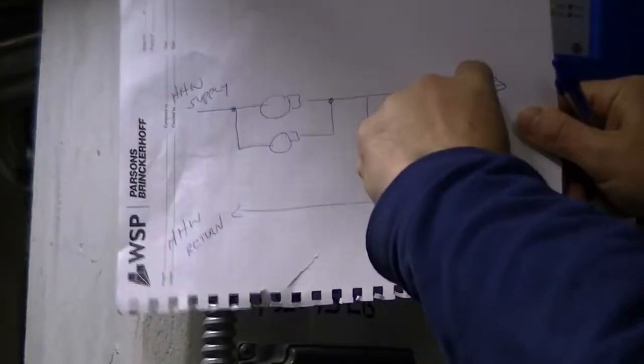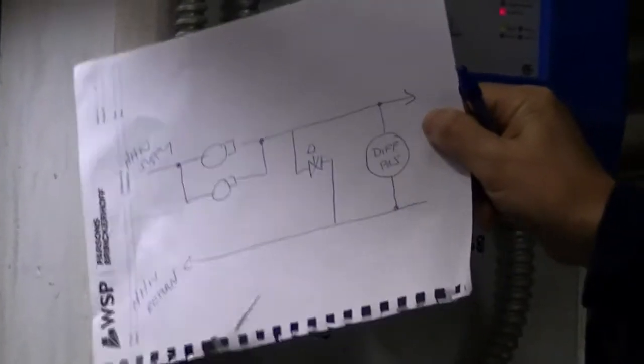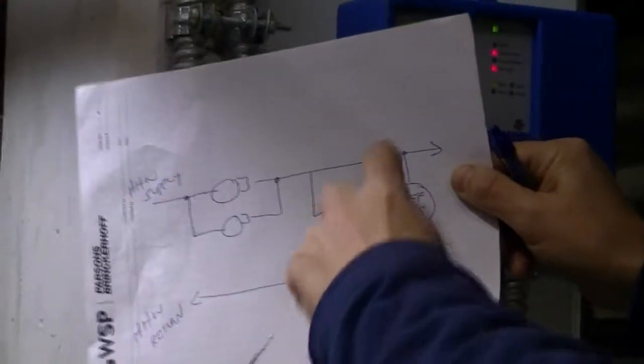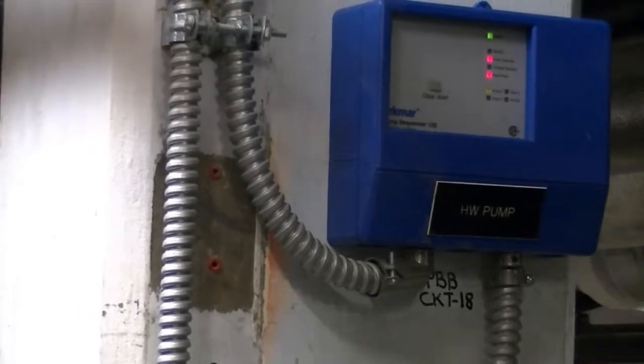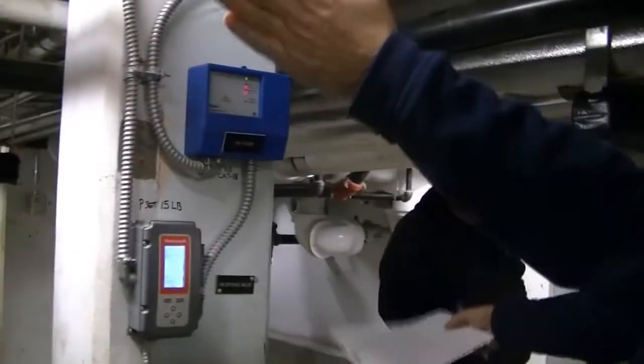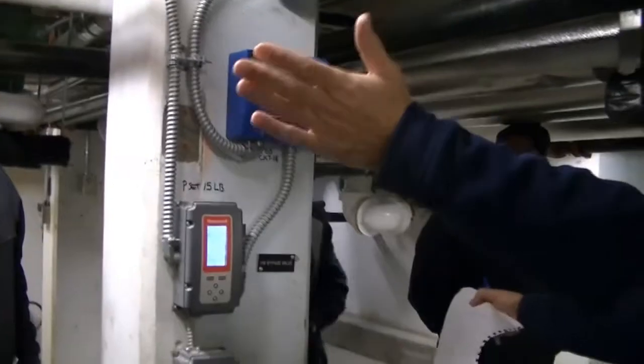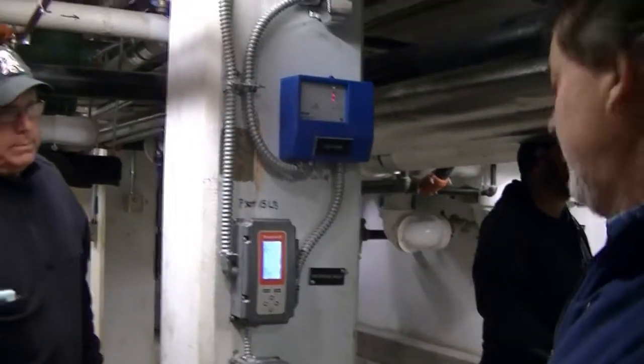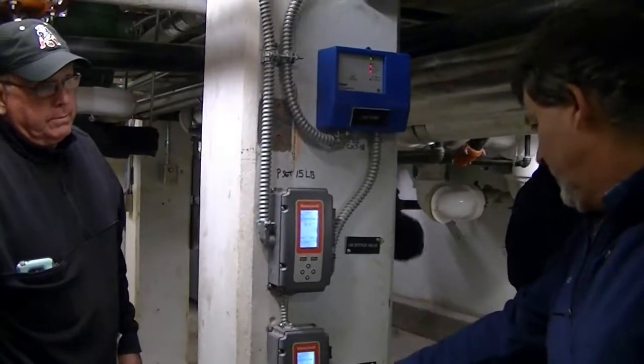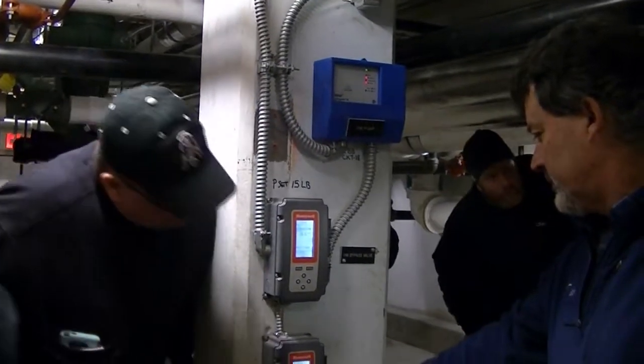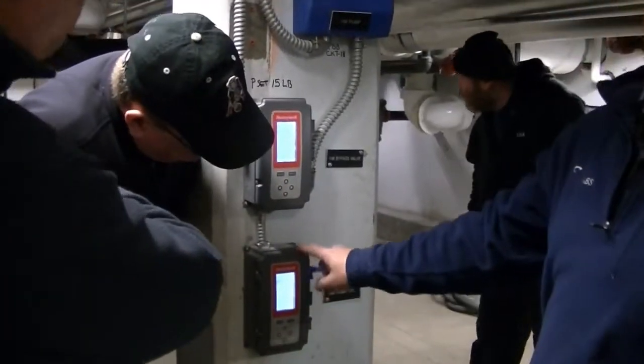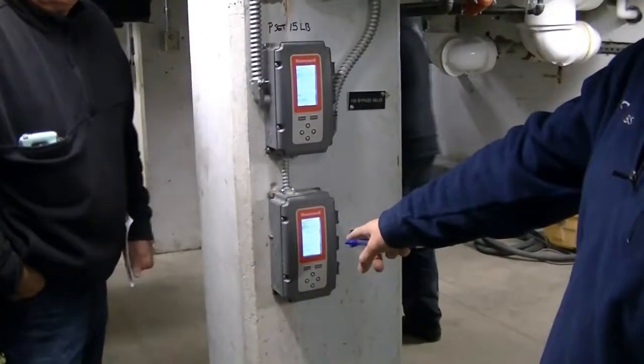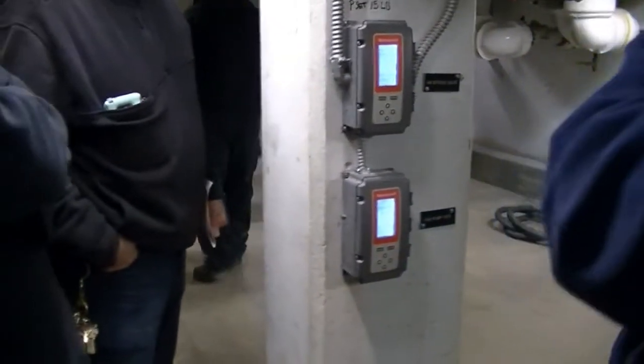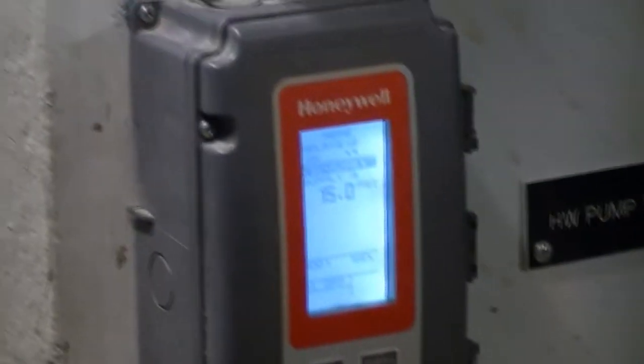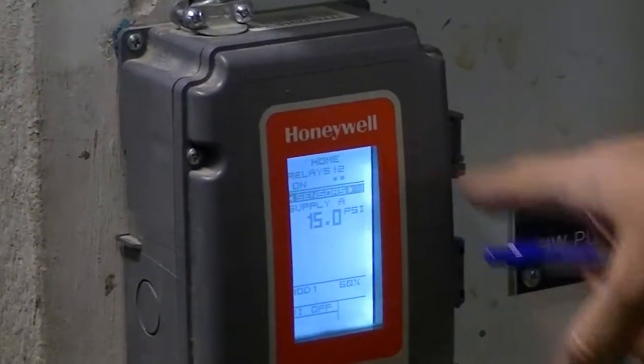So we got pumps going out. We have sensors here to measure pressure in PSI, okay? What this differential is looking at is it takes whatever the supply pressure is, subtracts whatever the return is, so you get a differential pressure. That differential pressure for your hot water pumps is what this thing tries to control at. So you give this thing a set point, and it will modulate the running VFD to maintain that set point. I believe this is set at 15 PSI.